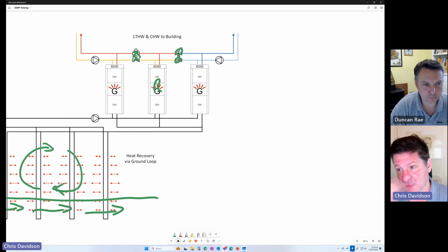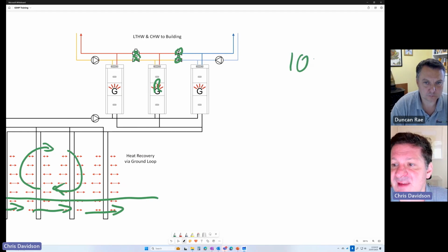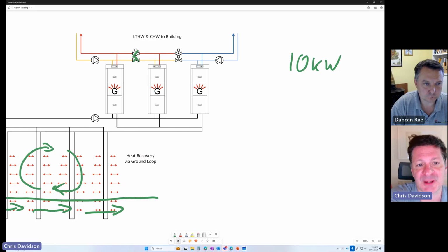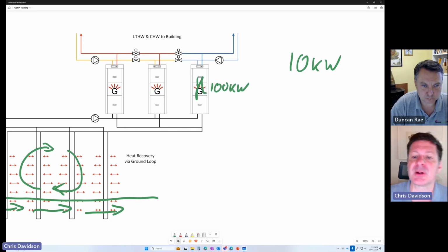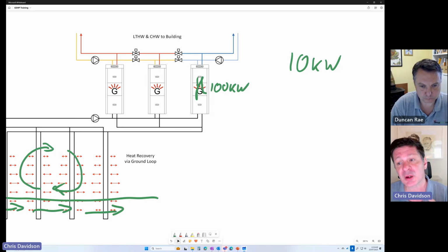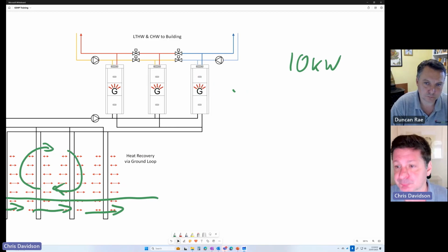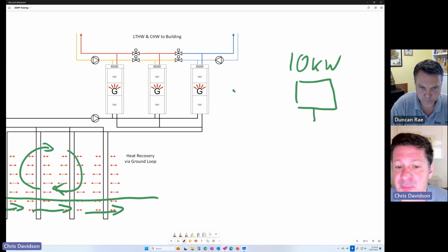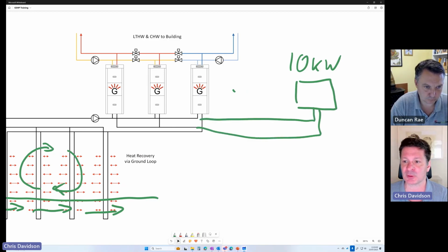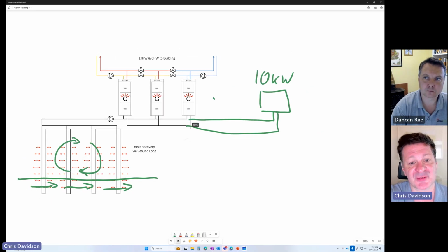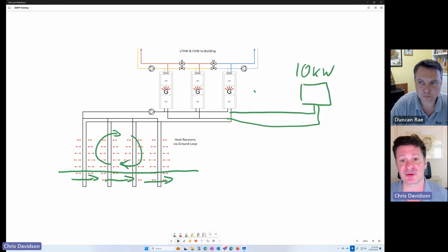And one very common mistake that's often made in these systems is, let's say we've got a small, say 10 kilowatt server room load that's all year round. And let's say we're now in the winter, we've got all our heat pumps here, all heating. To deliver that 10 kilowatt load, we've maybe got a 100 kilowatt heat pump here. And we'd have to reverse that heat pump, turn it on, and it's like accelerating, decelerating, putting your car in forward, reverse. It's very bad for both efficiency and the reliability, the longevity of that product. So a very common solution to this is to dedicate a small 10 kilowatt heat pump connected into the ground loop that will be doing that 10 kilowatt server room load. So a very basic system. There are plenty of other architectures for closed loop ground source systems providing heating and cooling, but that's just a typical one as an example.